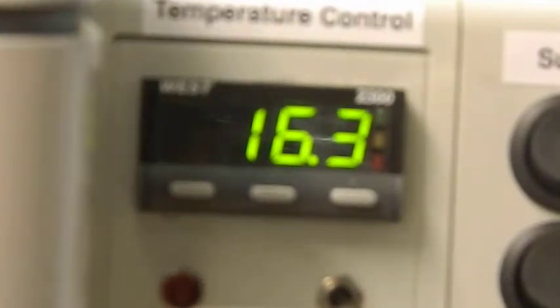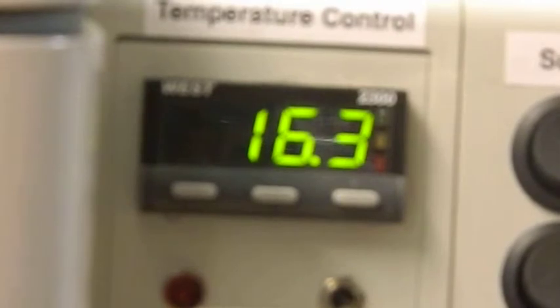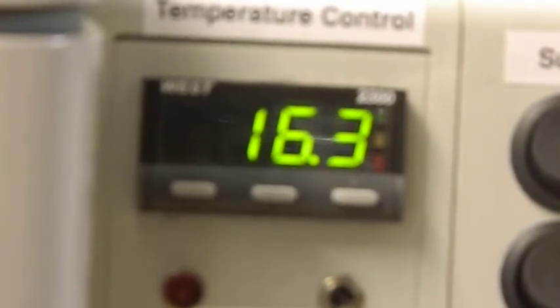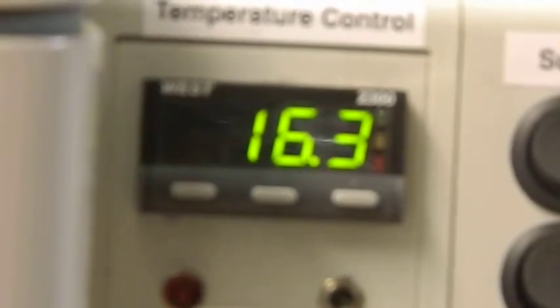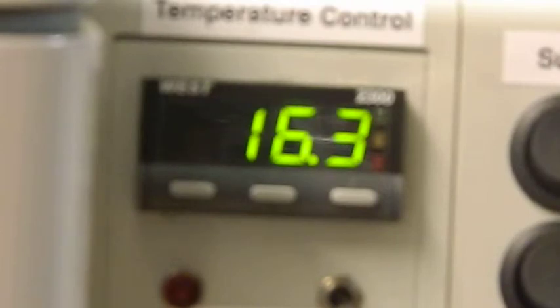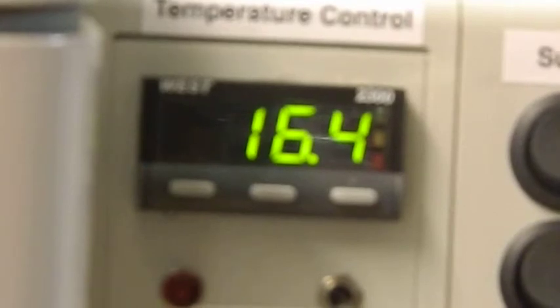Okay, today we're going to calibrate a West 2300 controller fitted to Mark 6 professional incubators. To do this, you need to understand that when the controller is new or when you've had a sensor change, the controller has no way of knowing exactly what the temperature differential is between its known value for a sensor and what the sensor reading actually is.